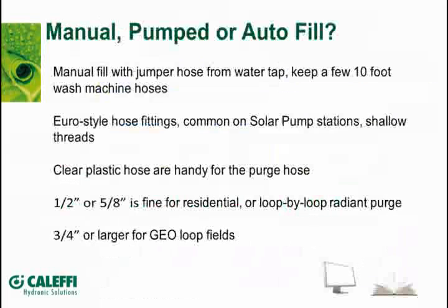Now, different ways that we fill a system. Manually, you can pump it in with, like I say, a little transfer pump, or you can use an autofill system. If it's going to be a water fill system, you want to put just a valve that's going to maintain the pressure. It's going to fill it and also maintain it when you walk away from it. So I'll go through a couple different options for doing that.